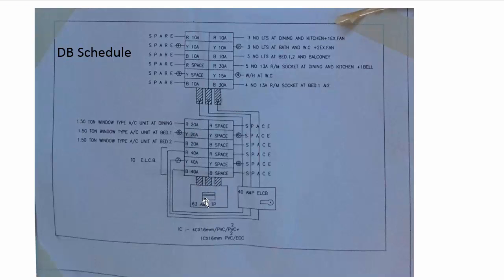The DB schedule shows the main breaker supplying a set of breakers, with one three-pole breaker tapping off to an RCD or ELCB which supplies the rest of the loads. Each entry in the figure shows the actual load connected to each breaker. For example, the top MCB, a single pole 10A MCB, protects three lights at dining and kitchen and one exhaust fan. The second MCB protects three lights at bath and water closet plus two exhaust fans and so on. We will go into more detail by looking at the plan of the flat.